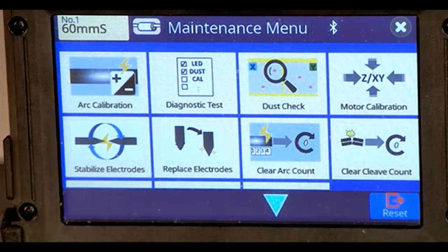This is the test I recommend you do probably once a week. I want you to do the manual arc calibration every day before you start splicing. But the full diagnostic test, where it checks the cameras and all that stuff, doing that once a week is usually enough. Sometimes when you call the 800 number, our technicians may ask you to do a full diagnostic check, because the results can help them troubleshoot whatever problem you're having with the splicer.